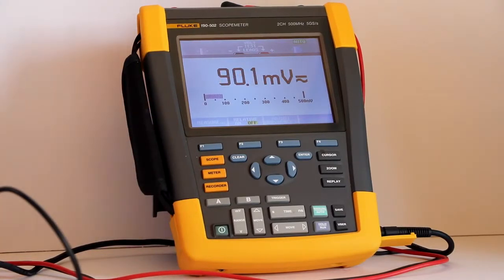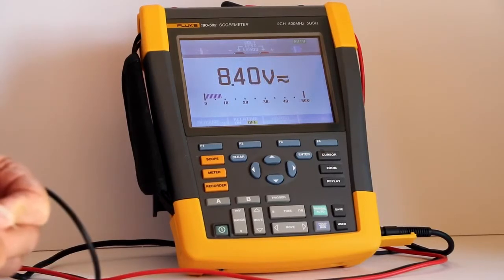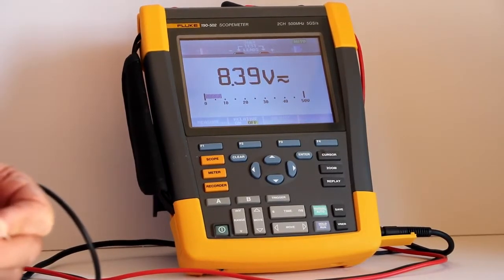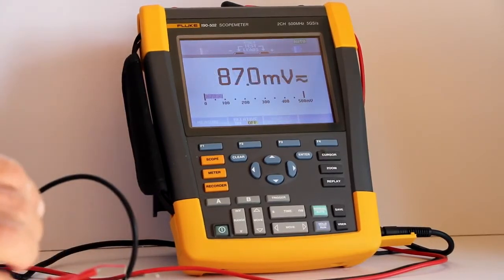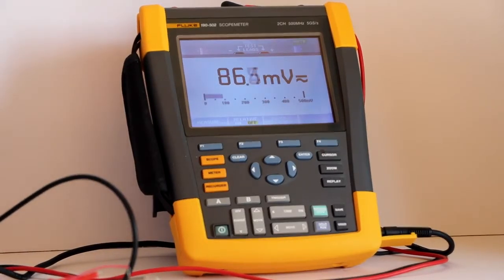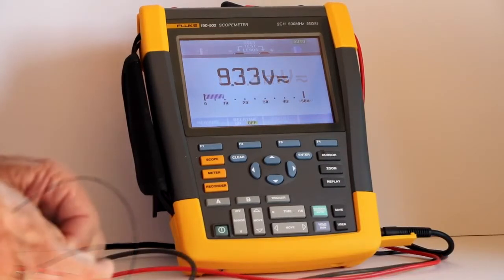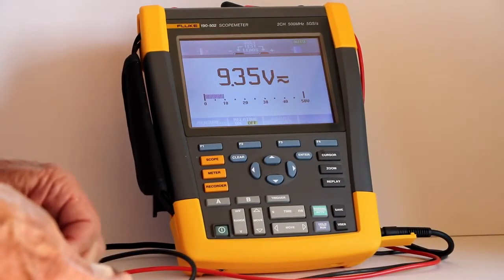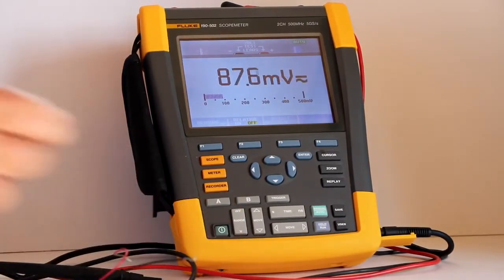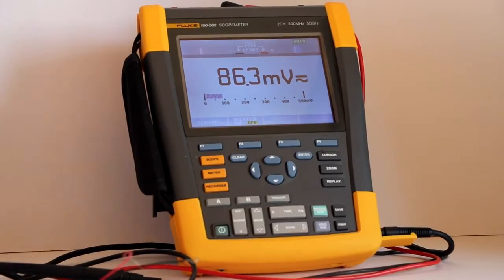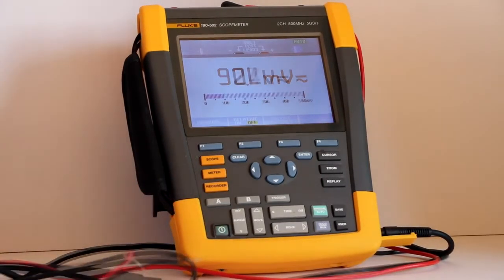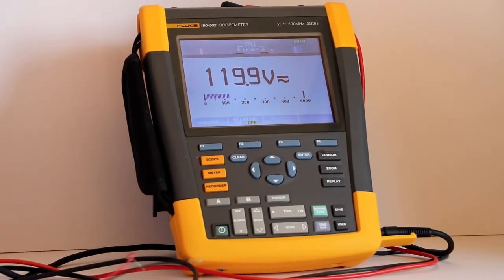First, a 9-volt battery. Notice that the voltage is 8.4 volts. This indicates only that the battery is low. We'll try another battery. Notice that the voltage is 9.35. That means it's a good battery, fairly new. Measuring AC utility voltage, the reading must be within normal range. Notice that the voltage is 119.9 volts, which is normal for a utility voltage.